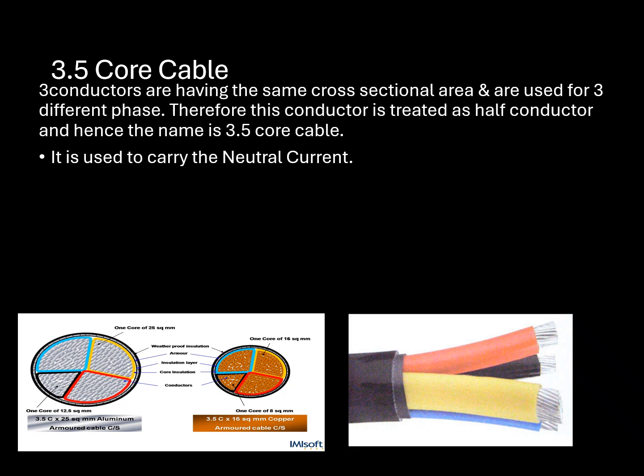Friends, we generally and mostly have 3.5 core cable. The 0.5 indicates half. So three conductors have the same cross-sectional area and are used for three different phases. And they have a neutral, which is treated as half conductor and has the name 3.5 core cable. The half portion is used to carry the neutral current. So you can see here, these three sector shaped are carrying R, Y, and blue phases, three phases. But the neutral goes in this half portion. That's why these are known as three and a half core.